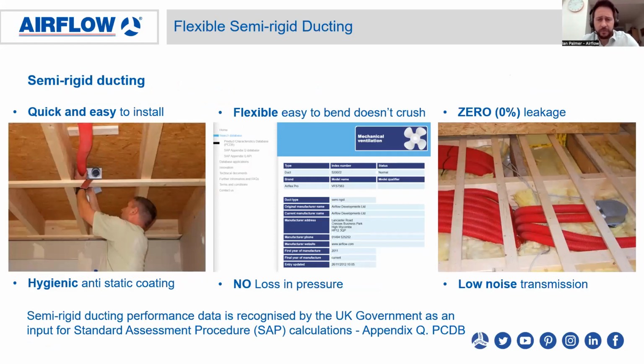So there is a mention of semi-rigid ducting, and semi-rigid ducting is known to be the most effective form of ducting to be used with a ventilation system. It's quick and easy to install. It's flexible, and you can bend the ducting and it doesn't crush like flexible ducting. There's zero air leakage. They are hygienic types of ducting systems. They've got an anti-static coating, so it means there's no dust and dirt buildup in the duct system. There's no loss in pressure, and there's no noise transmission.